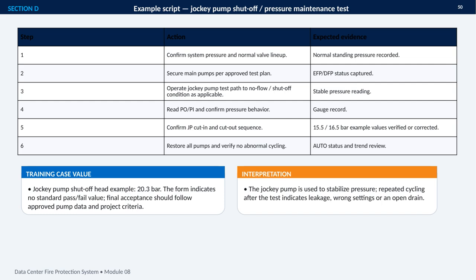The 20.3 bar shutoff head is an example, not a universal pass or fail limit. Final acceptance must follow the approved pump data and project requirements. After testing, I restore all pumps, confirm auto status, and review the trend for abnormal cycling. Repeated cycling may indicate leakage, incorrect settings, or an open drain.